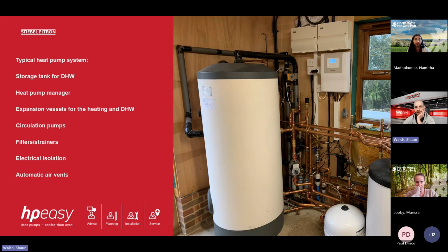This is for our domestic hot water, so our potable water for the property. Up on the wall here, we have the heat pump manager. The heat pump manager's job is to tell the heat pump when to run, tell the components what they need to be doing at any given time, and to monitor any sensors and flow rates and refrigeration pressure of the heat pump itself. Can't really see it, but the heat pump is housed just outside the window. So that's actually the part that's outside.